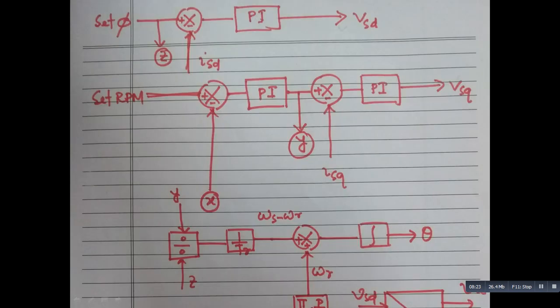Now, for setting the flux, I am basically setting the direct axis current, stator direct axis current. So it is compared with this block. Then this is a regulator. It is a PI regulator, which is generating the stator direct axis voltage.